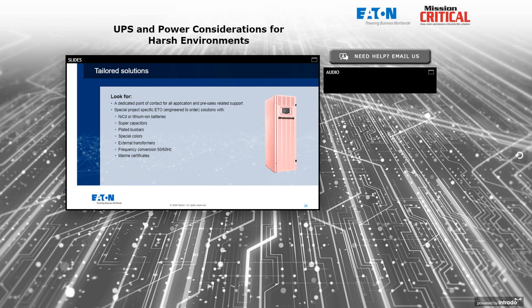NiCad batteries or lithium-ion batteries instead of traditional valve-regulated lead acid. Supercapacitors, otherwise known as ultracapacitors, for short backup time applications, either incorporated in the UPS or in a line and match cabinet. Metal-plated bus bars to avoid corrosion, external transformers or internal transformers, frequency converters. In other words, I have an application where I have 50 hertz utility input coming in, but the equipment I'm supporting needs to run at 60 hertz. So the UPS needs to take 50 hertz in and provides whatever voltage at 60 hertz out.